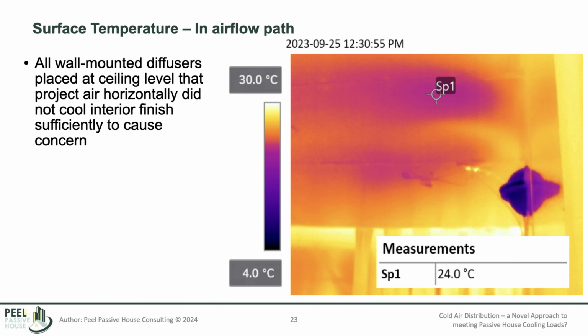And then if we look not just around the diffuser, but for these wall-mounted diffusers, what's the ceiling temperature doing? Basically we saw any diffuser that is essentially projecting air horizontally is actually not a problem. You can see the temperature there - you can't really go by the colors because the scale changes, but you can see the ceiling temperature and the air pattern is 24 degrees. That's 5-degree air coming out of the diffuser, and look how quickly it actually mixes and doesn't cause issues.